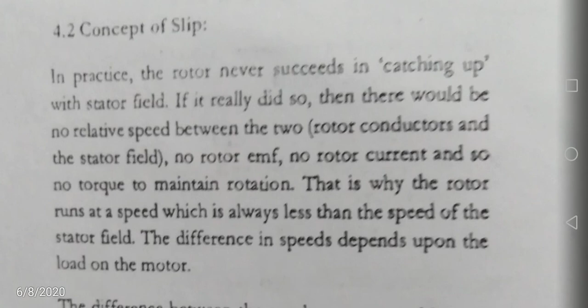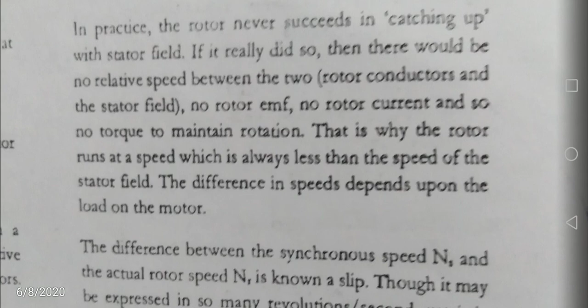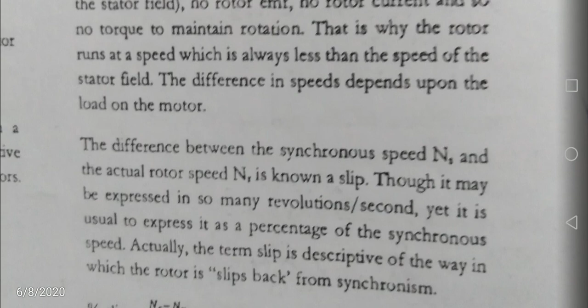Concept of slip. In practice, the rotor never succeeds in catching up with the stator field. If it really did so, then there would be no relative speed between the rotor conductors and the stator field, so no rotor EMF, no rotor current, and so no torque to maintain the rotation. That is why the rotor runs at a speed which is always less than the speed of the stator field. The difference in speeds depends upon the load on the motor.